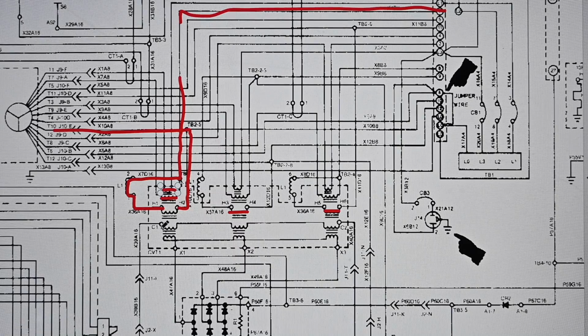We already looked at this control winding, and saw it has a DC voltage applied to it - ignore that for now. Let's look at this other winding right here, this one, and this one. You can see they're all connected together, common on one side. This comes down, comes over, has a common right there, and a common right there. The other side of the winding comes down and goes into the center of this three-phase bridge, and the same thing is happening here and right here - they're coming down to these common points on the bridge rectifier.